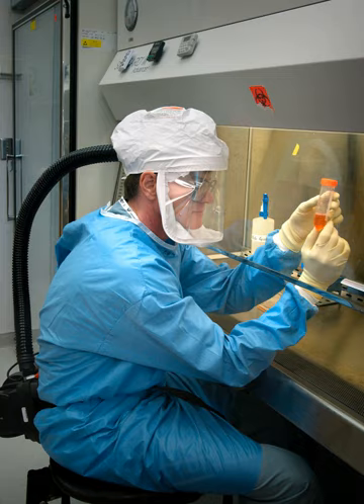Neither are most BSCs safe for use as fume hoods. Likewise, a fume hood fails to provide the environmental protection that HEPA filtration in a BSC would provide. However, most classes of BSCs have a secondary purpose to maintain the sterility of materials inside the cabinet.